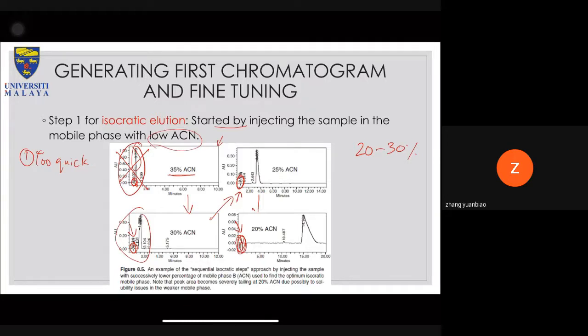So you go down to 25% ACN, you get a peak, something like that, and then you go down again to 20%, but then you see a peak tailing out. So you know that the limitation is 20%, because at 20%, once you see a tailing peak, it's either your sample now elutes very, very slowly, or there's some issue. There will be issues when you go lower than 20%. So now your limit is between, I would say, 30% to 20%. So by doing this, 25% might be the best for this initial run. So you start off with 25 and then you further optimize it. Okay, so that's how you do it if you do an isocratic elution.